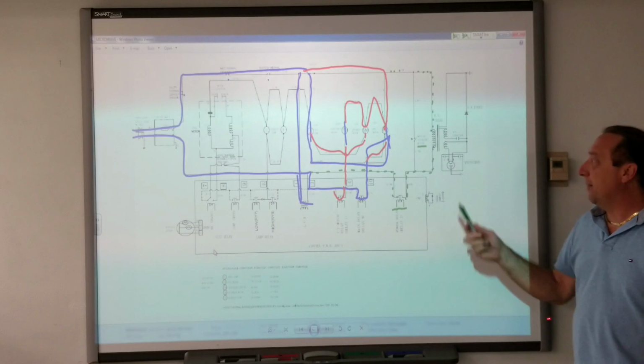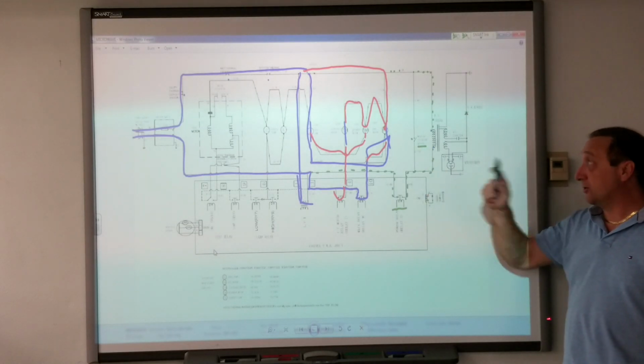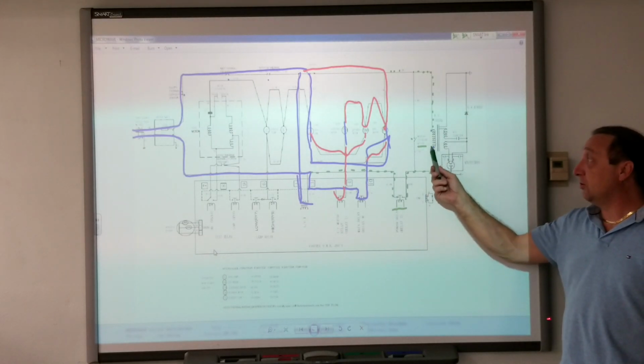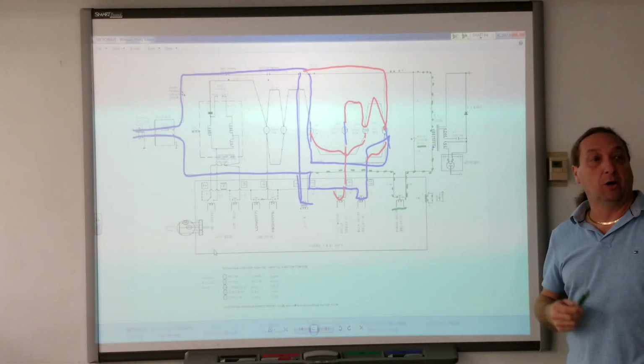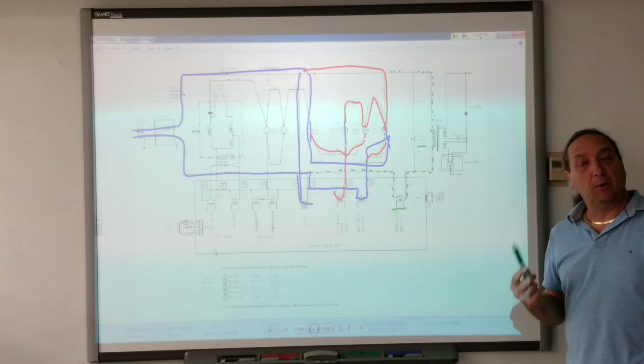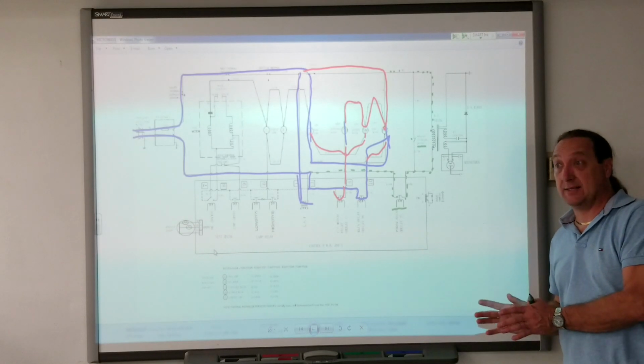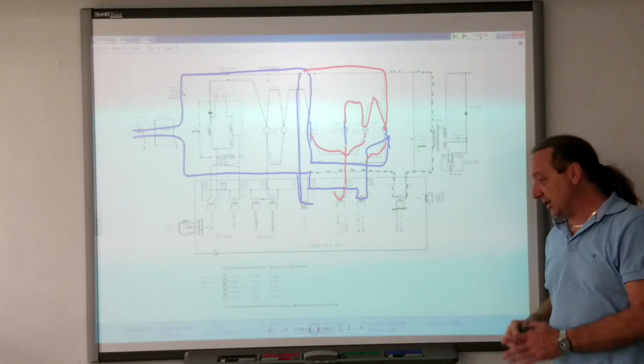So our problem is not the monitor switch. What we need to do first is check power to the transformer, and make sure we're testing the right side, the primary voltage side.